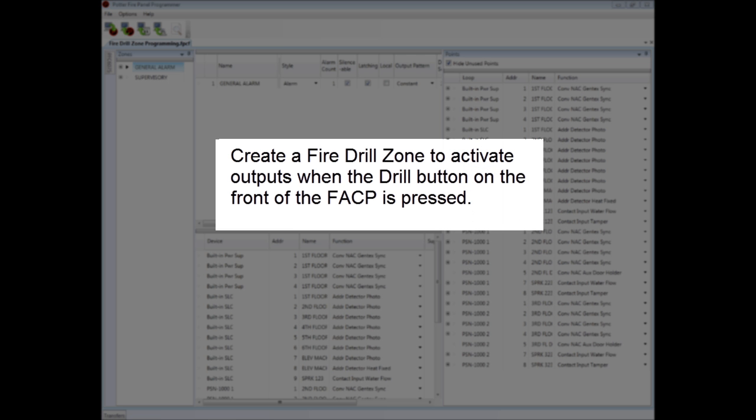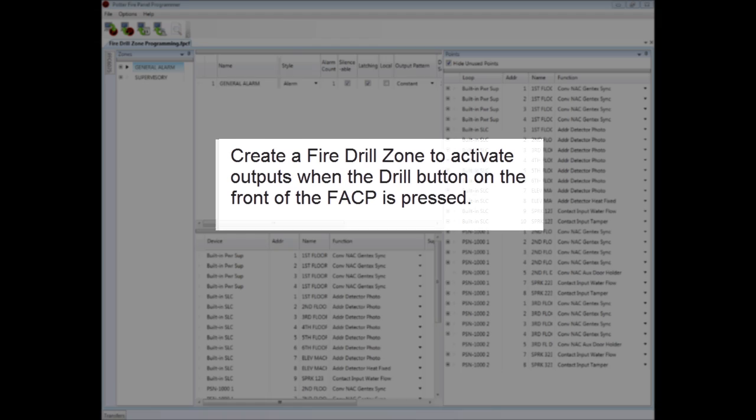On the PFC 6000 series fire alarm control panels, in order for the drill button on the front of the fire alarm control panel to activate the notification circuits that you want to activate in a fire drill, you need to create a fire drill zone in the programming software.